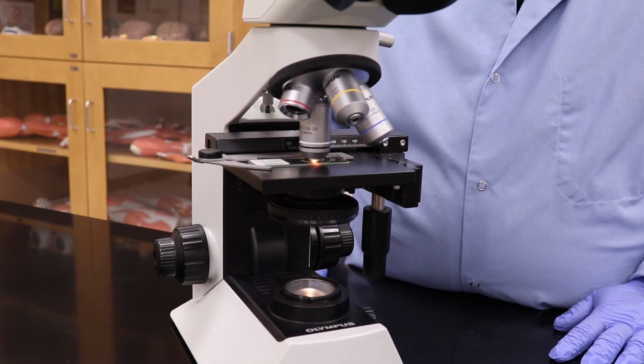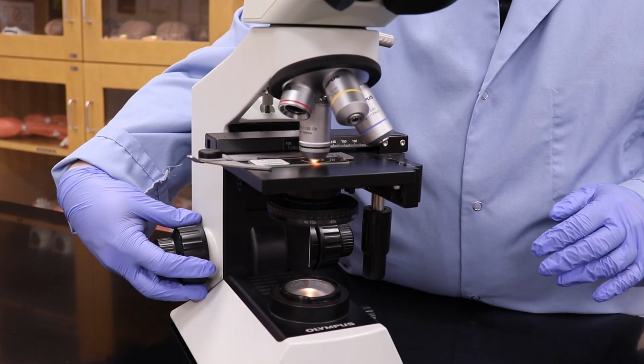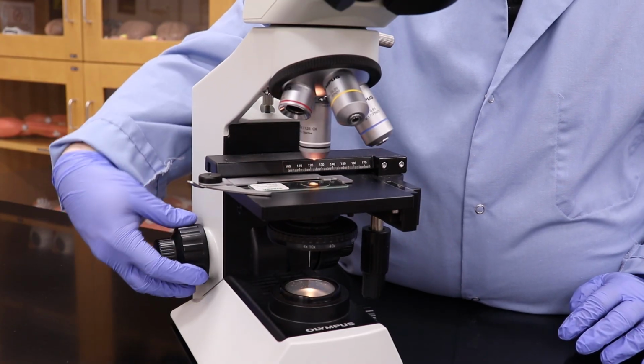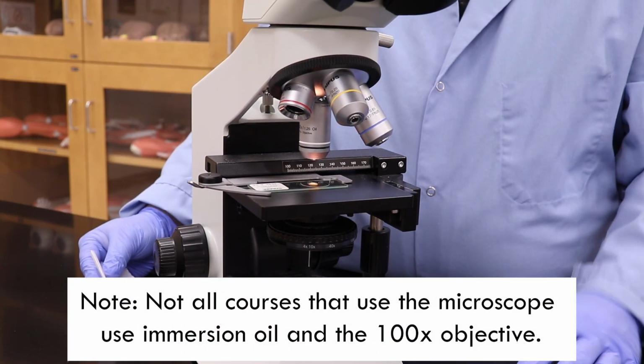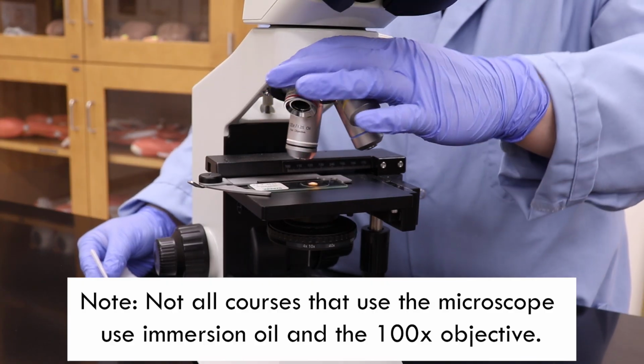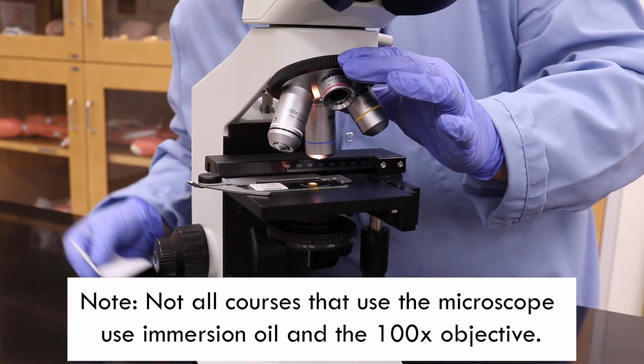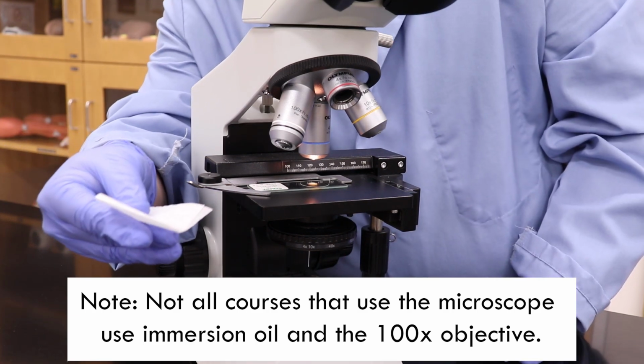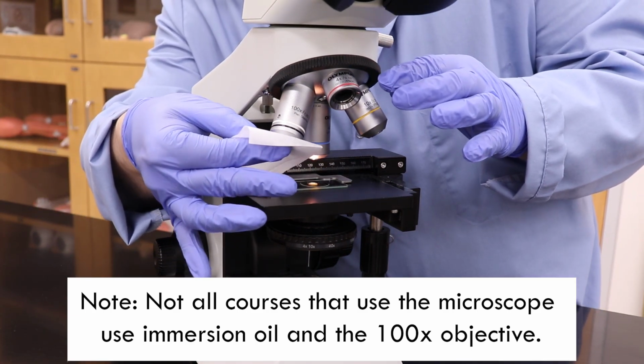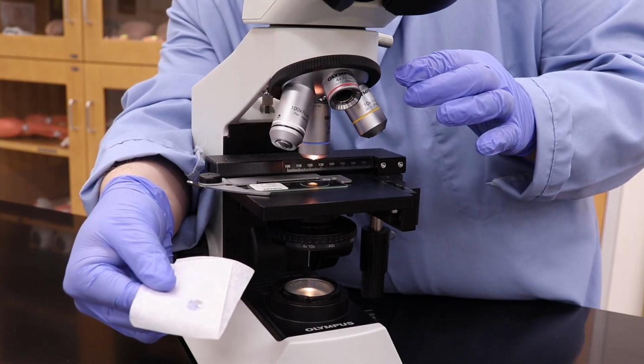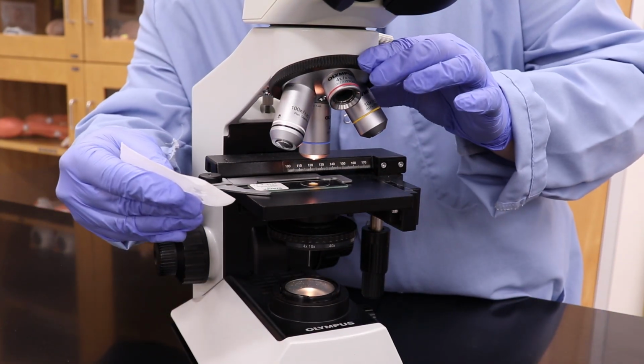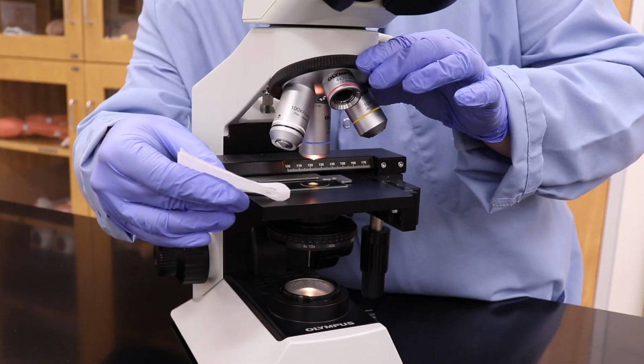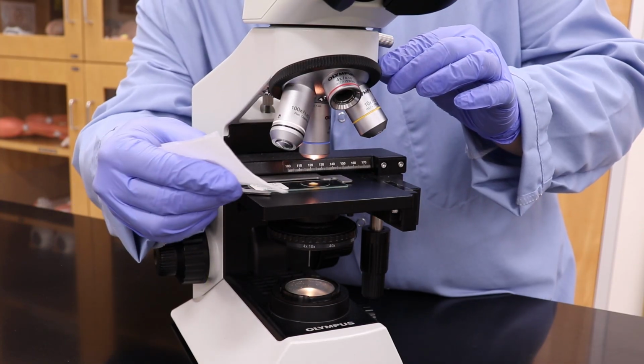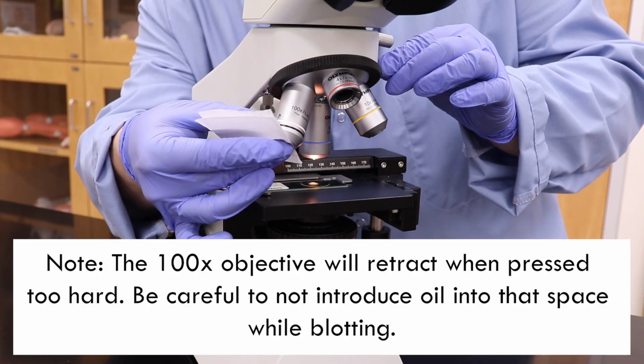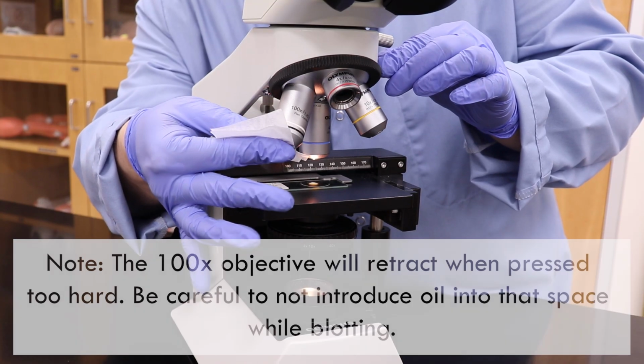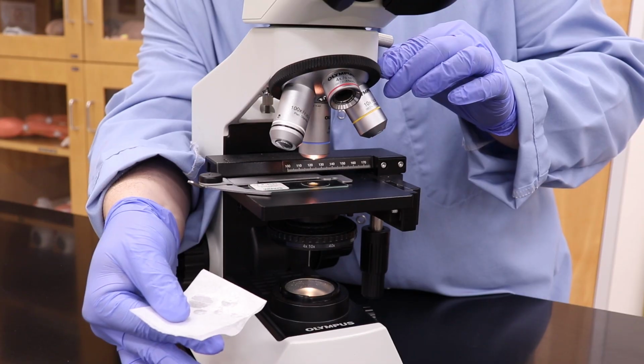Next, we will be moving on to cleaning the objectives. First, you will drop the stage using the coarse focus knob. Once the stage is lowered, you'll use the nose piece to twist the 100x objective out of the way. Then you'll take a piece of lens paper and gently blot it to remove any immersion oil. Immersion oil is used only for the 100x objective to make sure that the image is clear. Immersion oil needs to be removed after every use using this blotting technique. Keep blotting until no oil comes back on the lens paper.